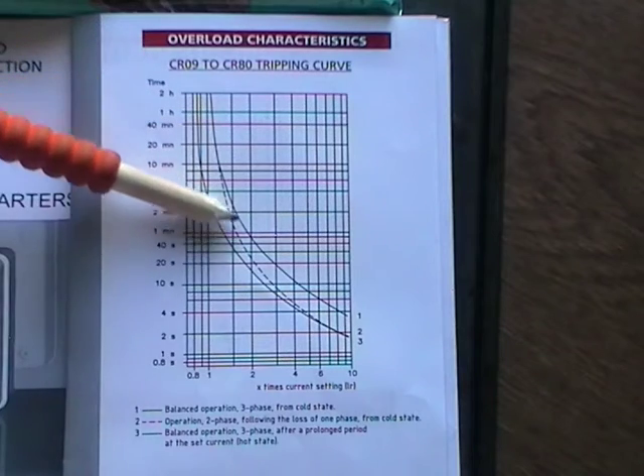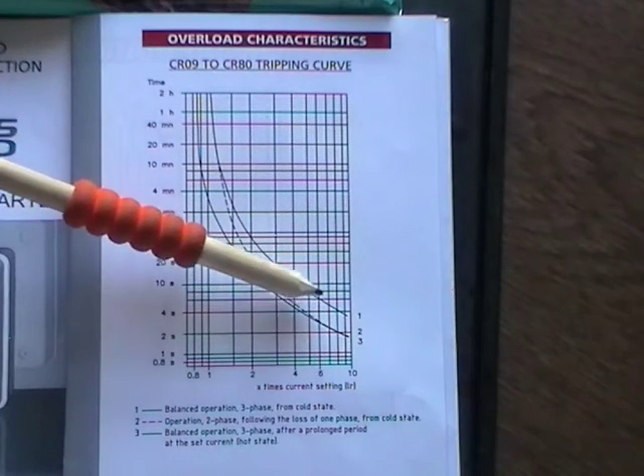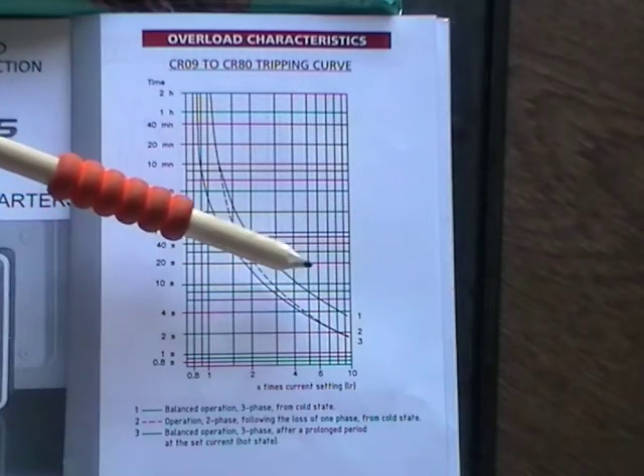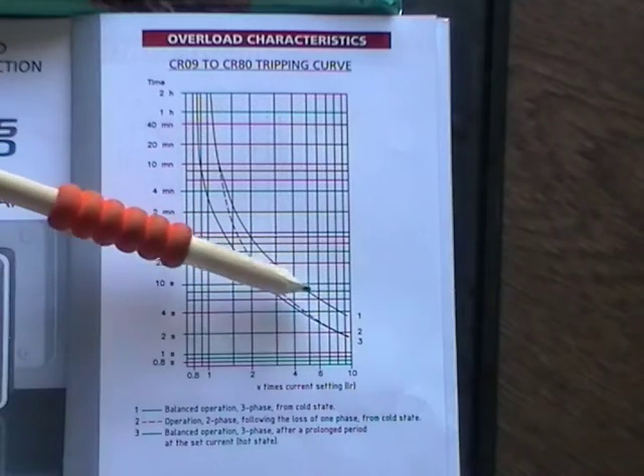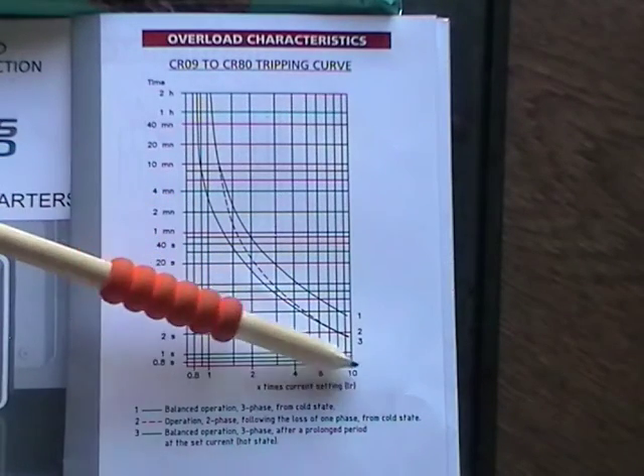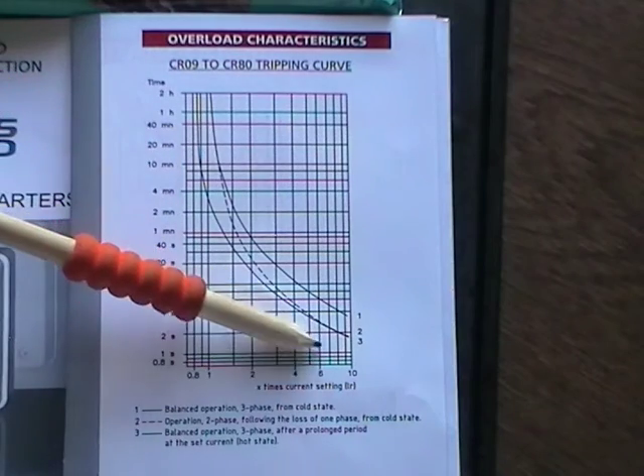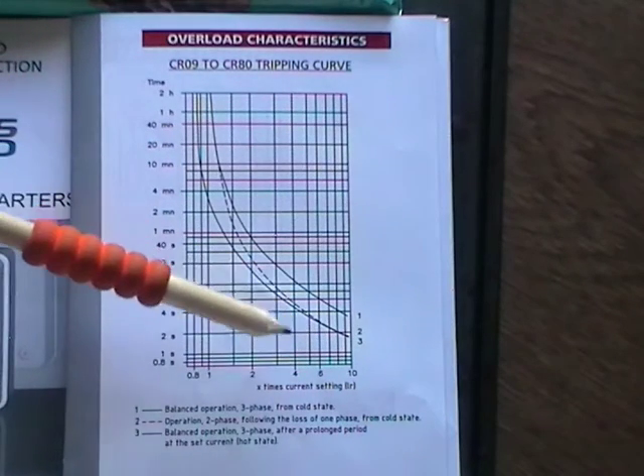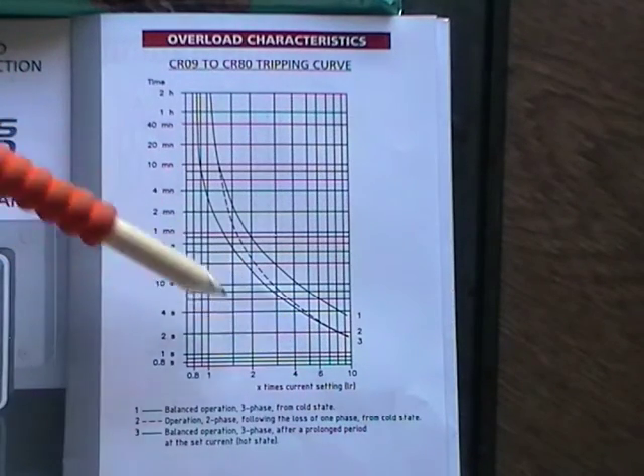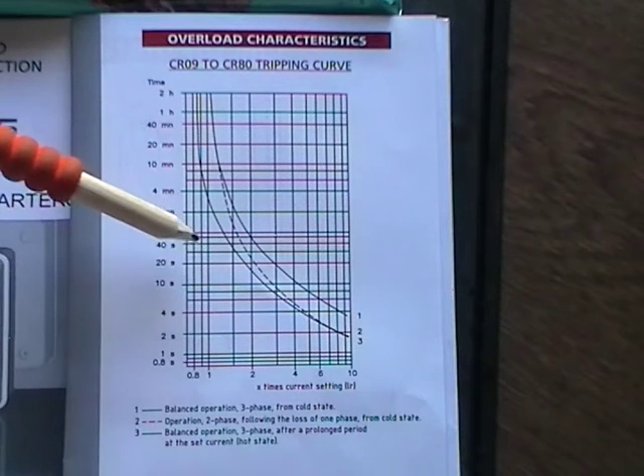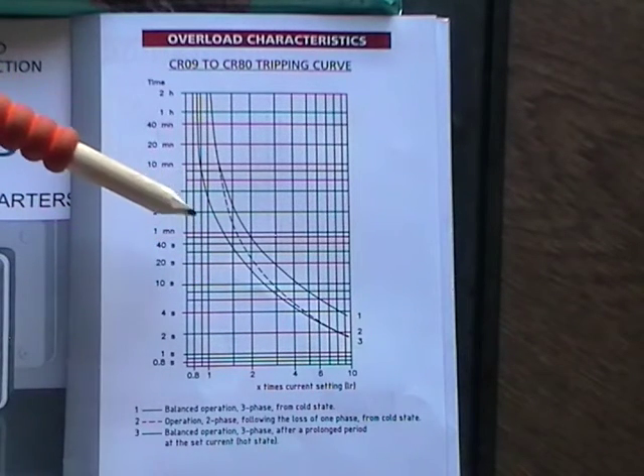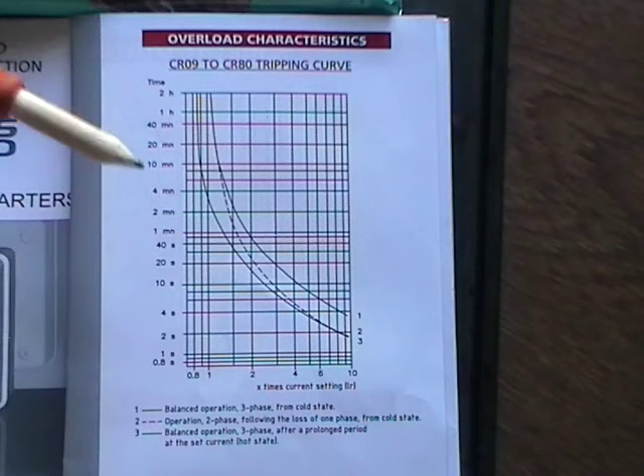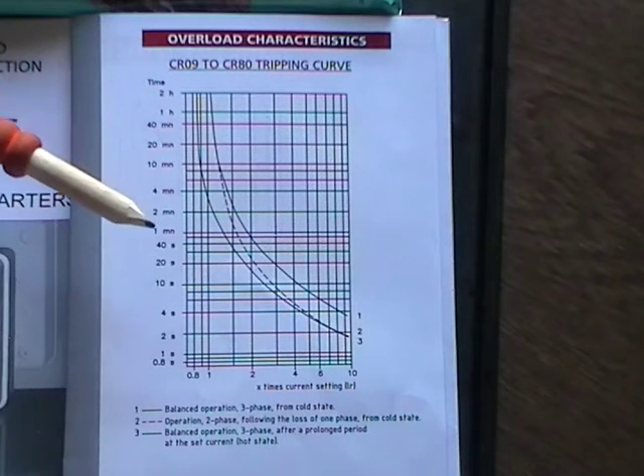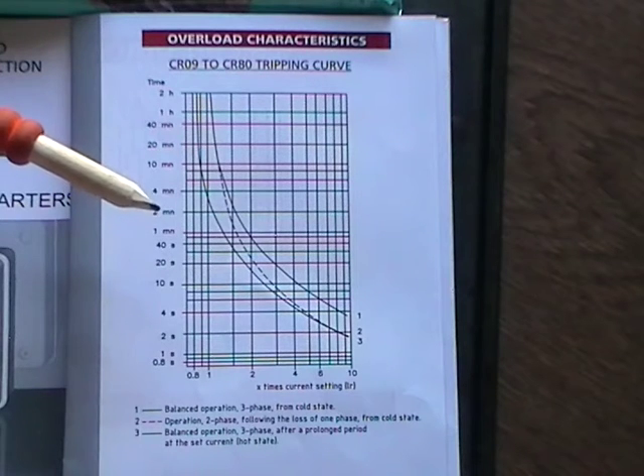The number 1 curve is with a cold system, so as if the motor's not been run, and the number 3 curve is for a motor that's been running for a few hours. The trip levels change with time as the trip warms up and the motor warms up, and this is correct operation to take into account the temperature of the motor before a particular load is applied.